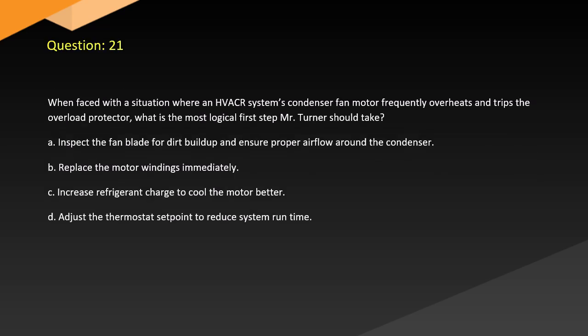Question 21. When faced with a situation where an HVACR system's condenser fan motor frequently overheats and trips the overload protector, what is the most logical first step? Mr. Turner should take: A. Inspect the fan blade for dirt buildup and ensure proper airflow around the condenser. B. Replace the motor windings immediately. C. Increase refrigerant charge to cool the motor better. D. Adjust the thermostat set point to reduce system runtime.